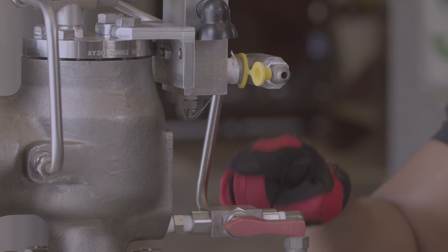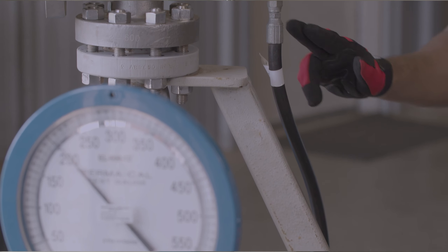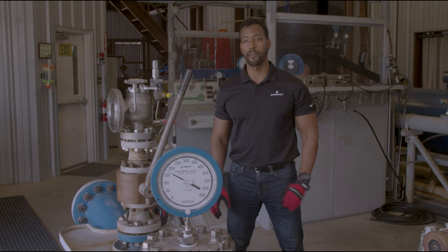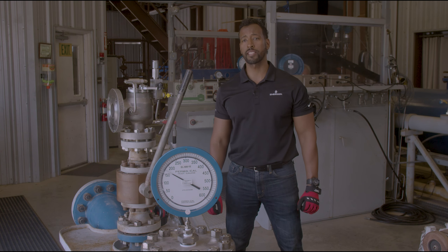What I have set up here is the 200 Series Pilot with an integral sense connection on one side of a 3-way ball valve and a remote sense connection on the other. This hose simulates the remote pressure sense line back to the vessel that the valve is protecting and is connected back to our test vessel.